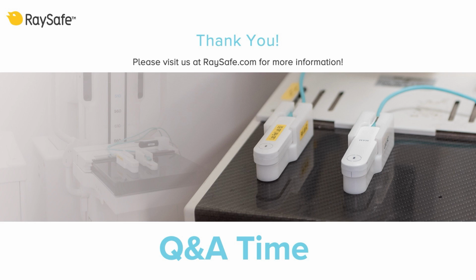Can the 452 measure high dose rates? Yes. The 452 has a wide dynamic range, starting at background all the way up to 1 sievert or 1 gray an hour, which is the same as 114 Röntgen per hour. And this wide dynamic range is thanks to the combination of the GM pancake and the solid state sensors, which we presented in the presentation.